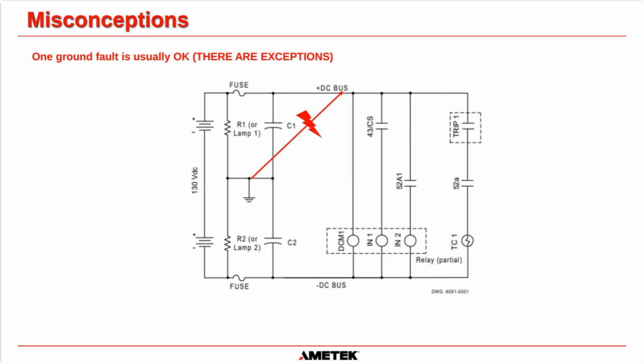example of it. It's just basically, remember, two resistors of identical value in series connected in parallel across the DC create a potential divider. So yes, you are going to get basically 65 volts there and 65 volts there. And the capacitors just add some stability to that potential divider. So that's what this circuit part is here. Okay. And this is what we're controlling. So it's probably a tripping and closing supply for a big MCC breaker.